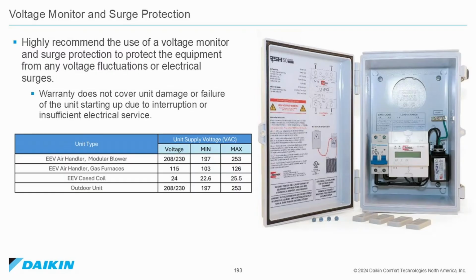On the chart below, you'll see that an EEV air handler and modular blower, which operates on 208 to 230 volts AC, will operate from a minimum of 197 to a maximum of 253 volts. The EEV air handler and gas furnaces that are 115 volts will operate from a minimum of 103 to a maximum of 126 volts. EEV cased coils, which operate on 24 volts, will operate from 22.6 volts to 25.5 volts maximum. The outdoor unit, which is 208 to 230 volts, will operate from 197 minimum to a maximum of 253 volts.